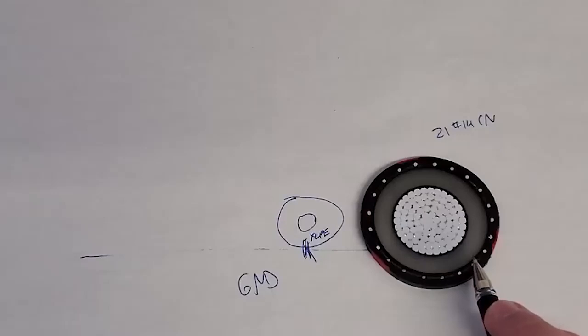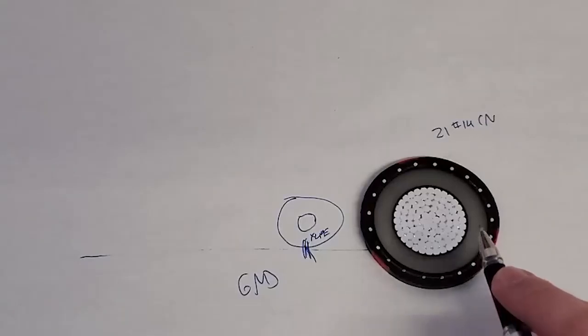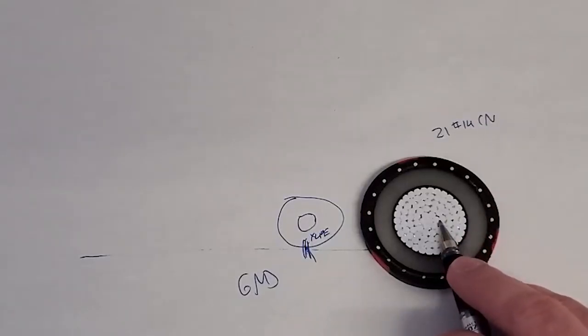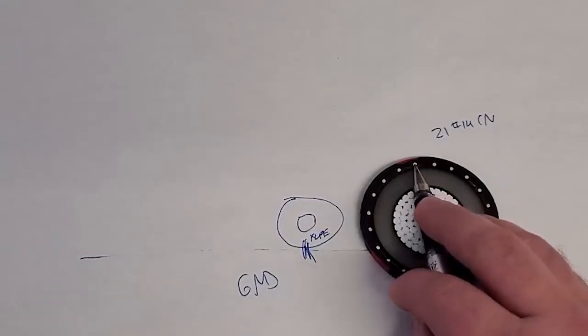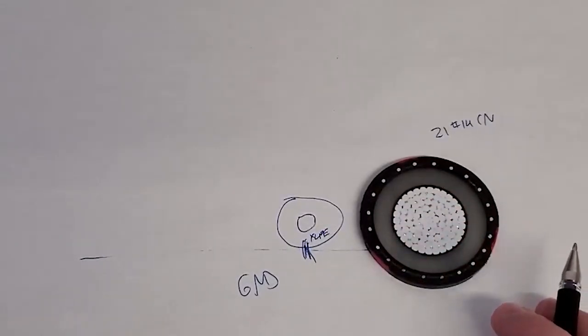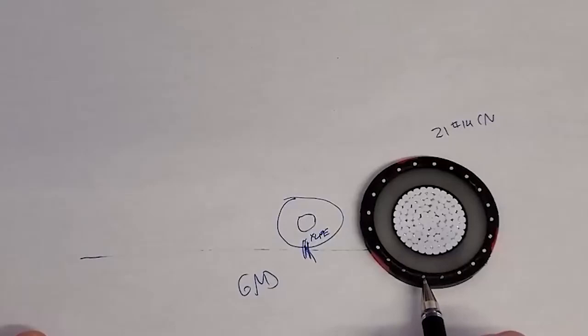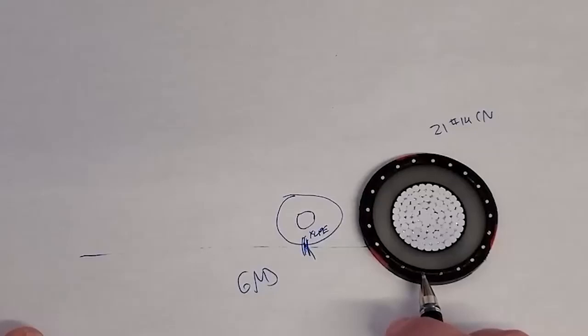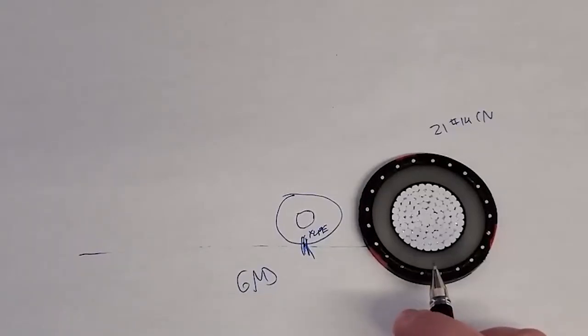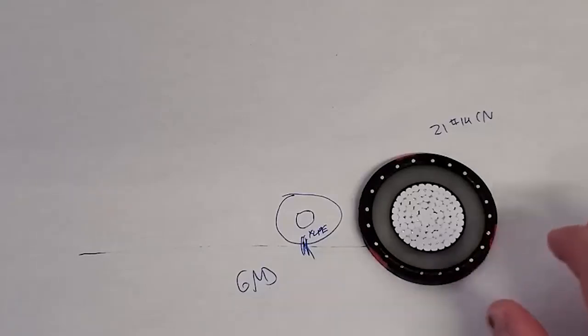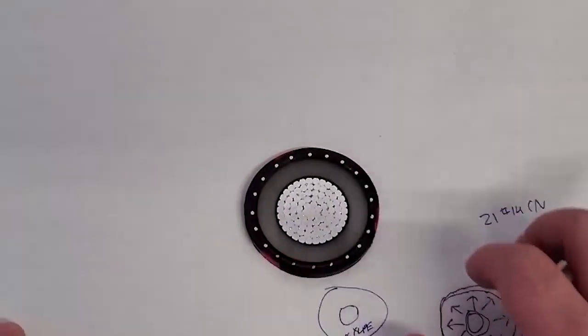And probably the item that affects the cost of this cable the most, number one is the size, because you're going to have the most material. And the second one is your concentric neutral layer. Why is that? Well, it's because it's copper. Copper is a lot more expensive than the aluminum. So the name of the game, really, with the engineers is to have them run their fault current study and determine the minimum size concentric neutral required for that project to maintain a safe project. So you want to put a lot of time and money into that, because you'll get that money back in being able to potentially reduce your concentric neutral. So very important for that.